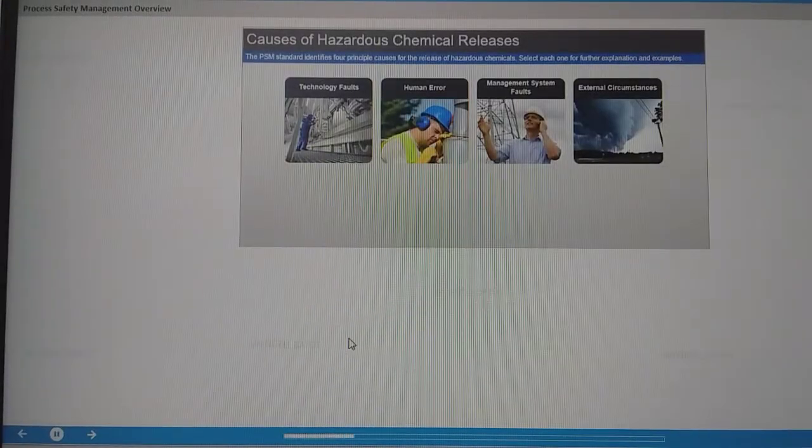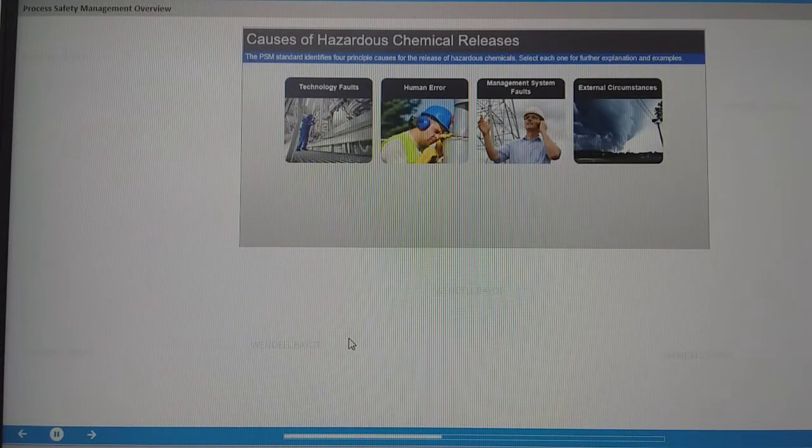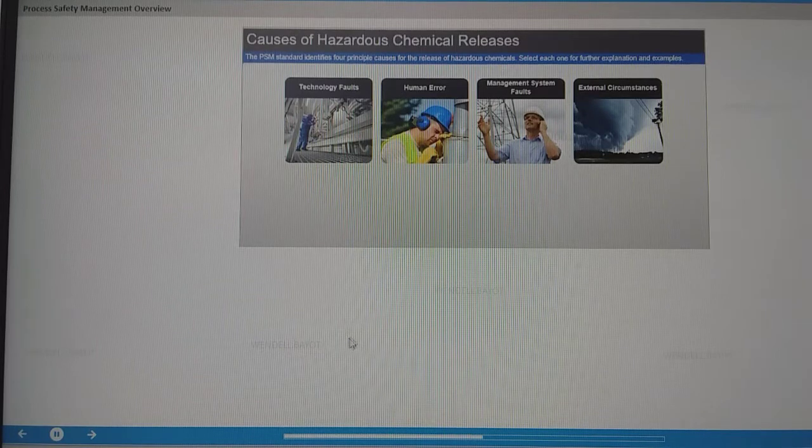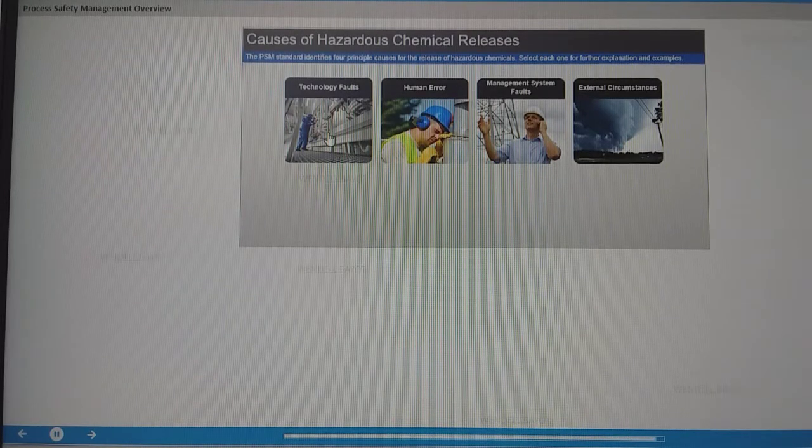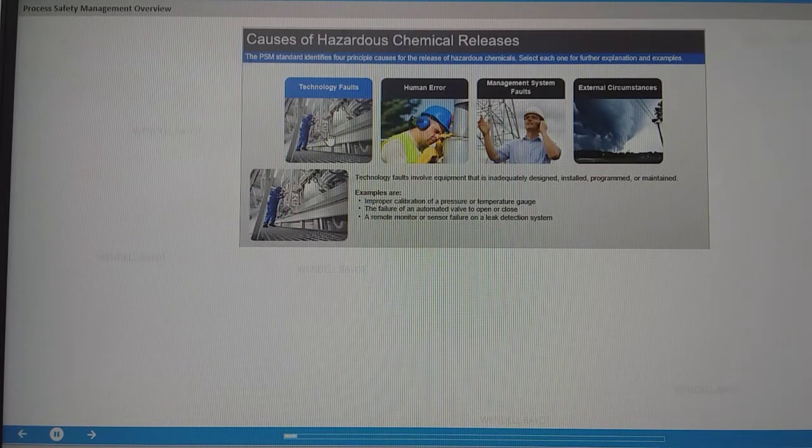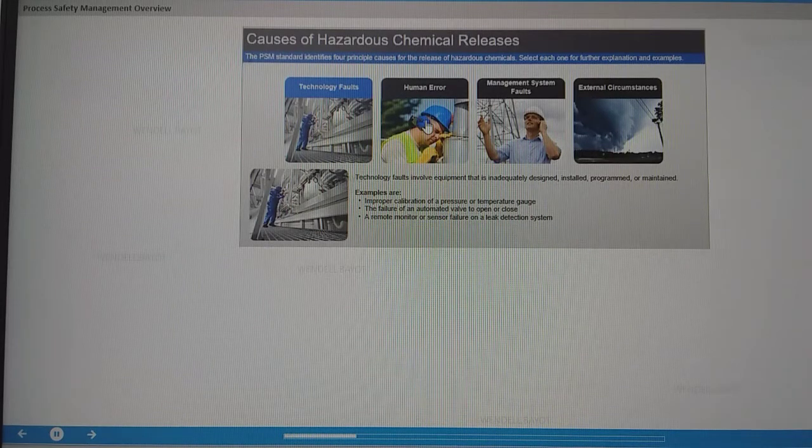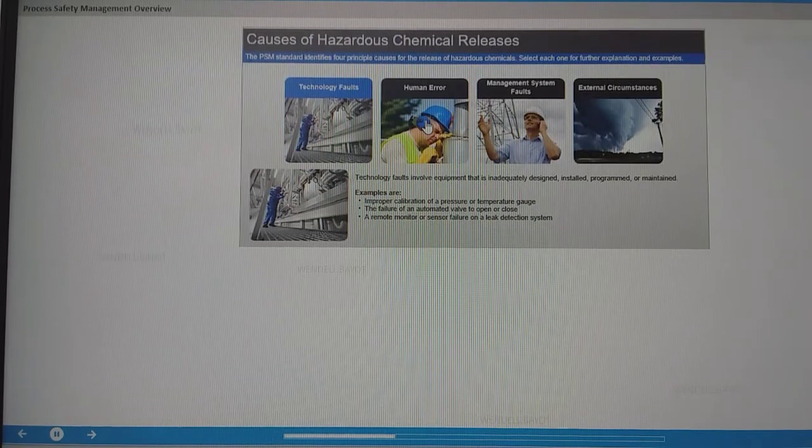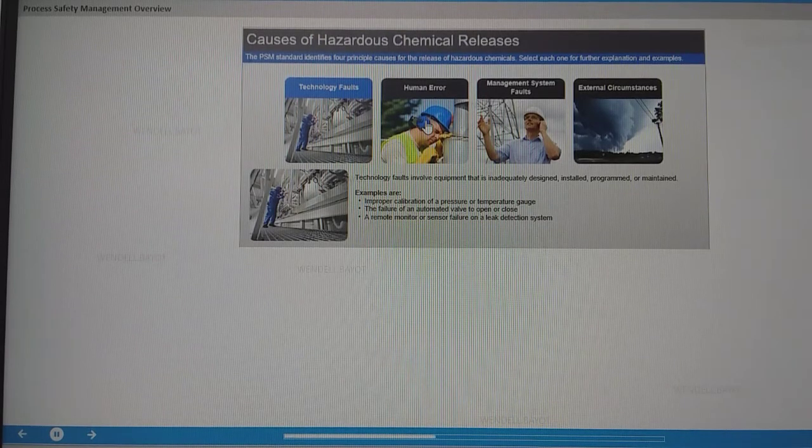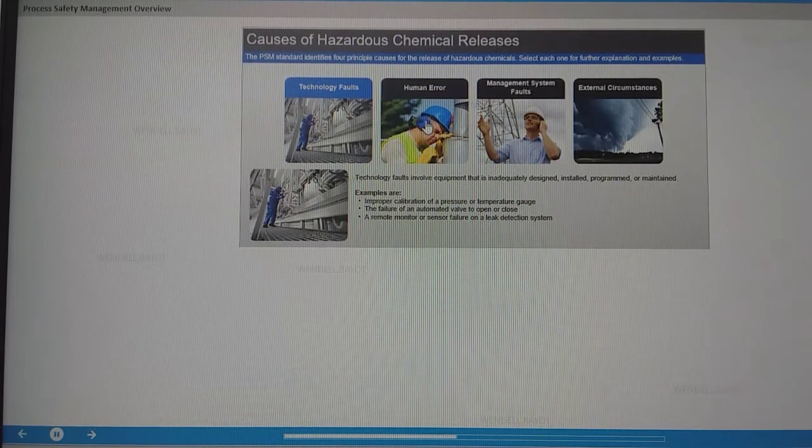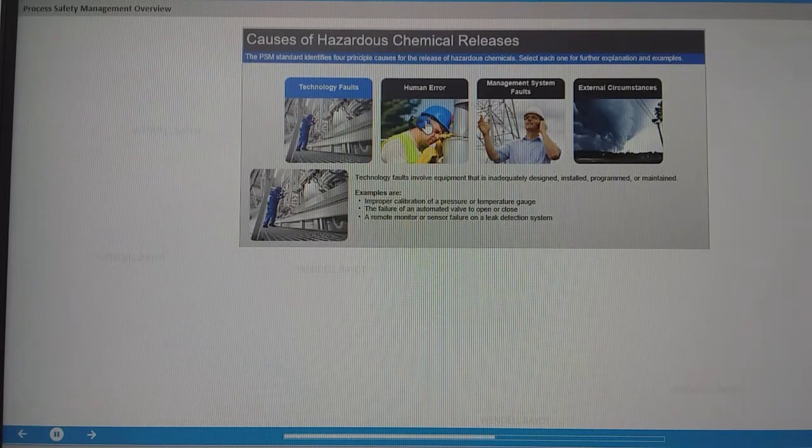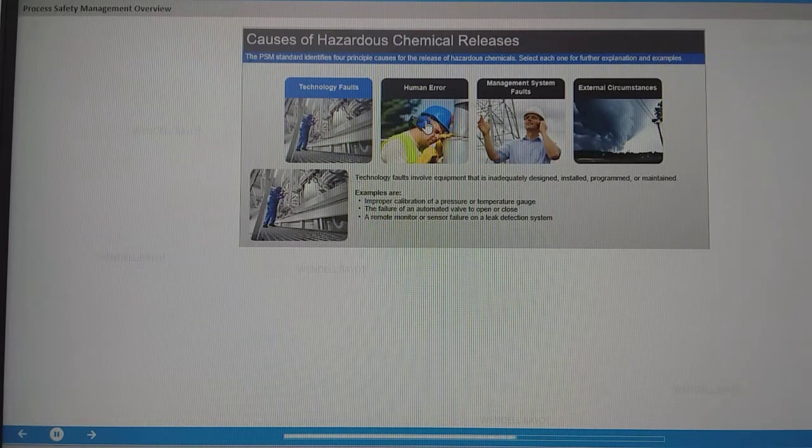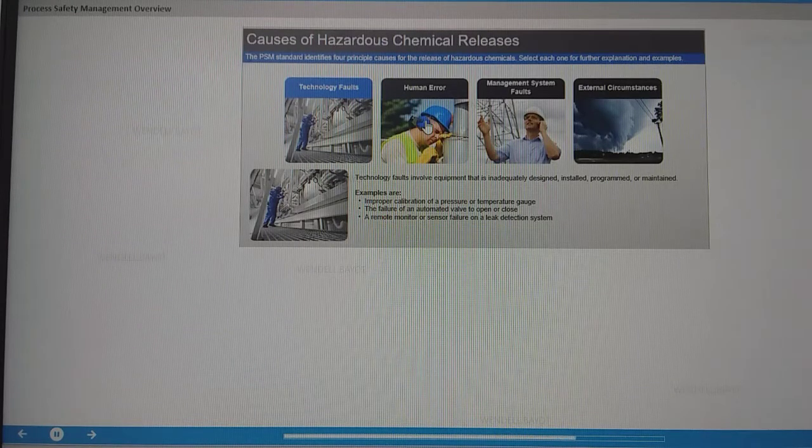The PSM standard identifies four principal causes for the release of hazardous chemicals. Technology faults involve equipment that is inadequately designed, installed, programmed, or maintained. Examples are improper calibration of a pressure or temperature gauge, the failure of an automated valve to open or close, and a remote monitor or sensor failure on a leak detection system.